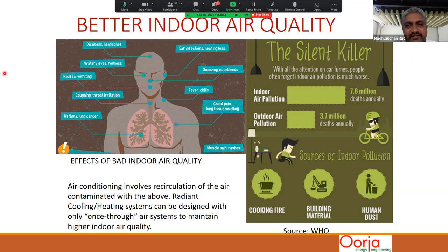So the remaining latent and fresh air load needs to be handled by the TFA, or in the radiant cooling parlance, it is called DOAS, dedicated outdoor air system. So when you use that, you can have just once-through air. And when you have once-through air, your chances of infection or recirculation of some of the biocontaminants can be significantly avoided.